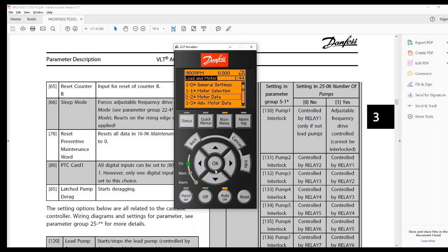So the different AMAs, and as we saw, we're going to cut these into 2 different parts. So we have a complete AMA, which tunes all the reactance and resistance, and there's a reduced. The difference between, like I said, when I would use them, the reduced only does the main resistance. And I would always do the complete, but sometimes certain motors, or let's say there's more capacitance in the cable and stuff, this will fail. It can't get all the correct numbers, or it doesn't settle out.